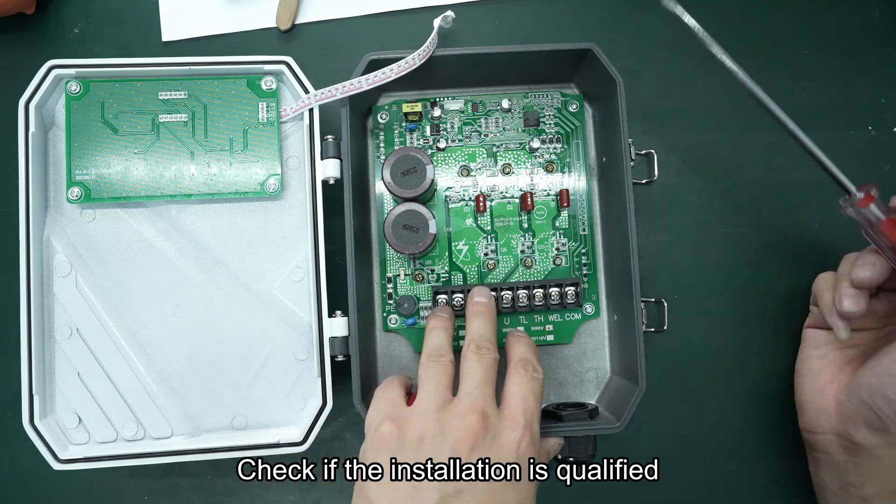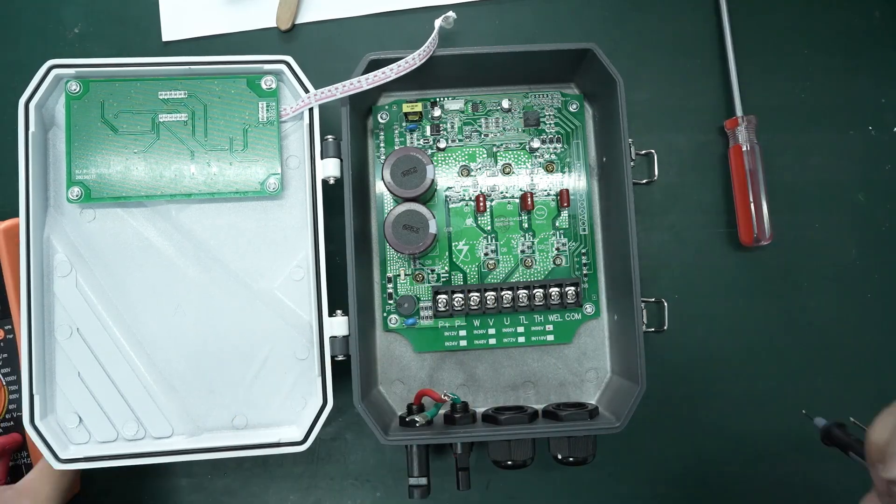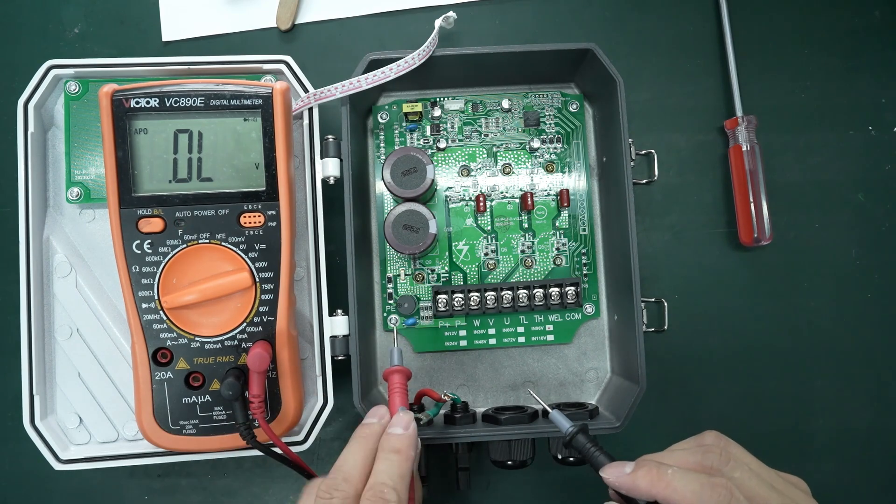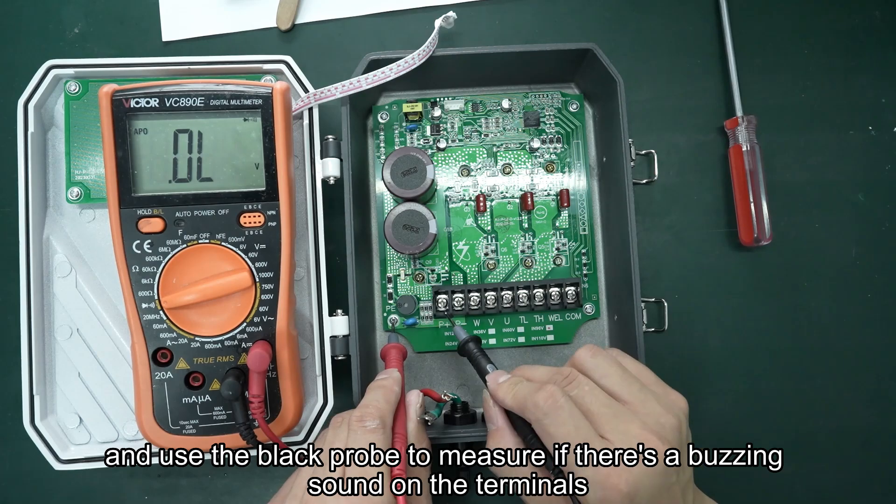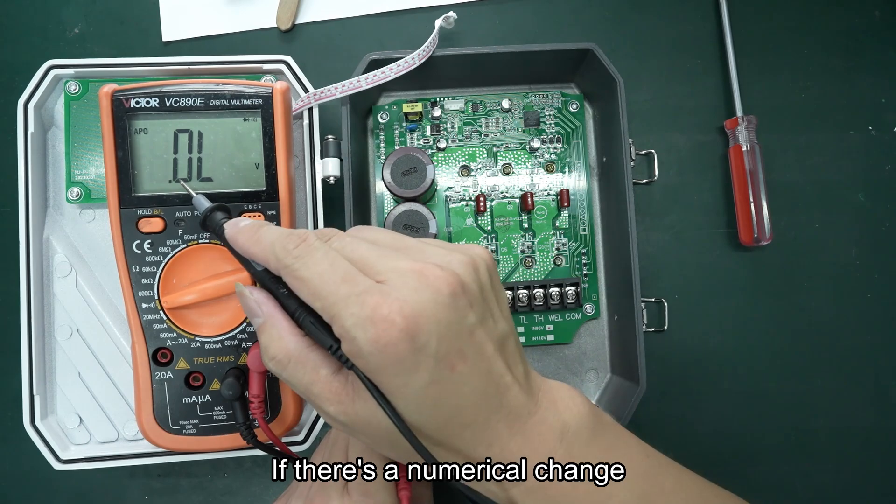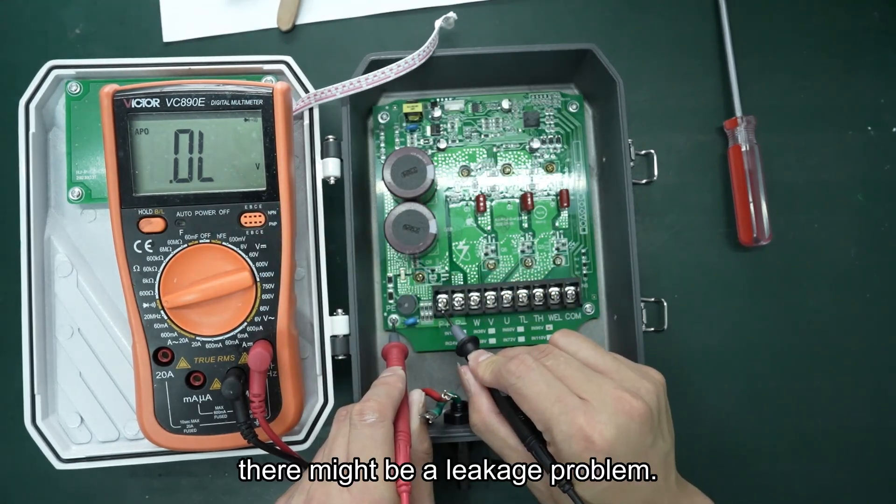Check if the installation is qualified. Use the buzzing mode on the multimeter. Place the red probe on the PE position and use the black probe to measure if there's a buzzing sound on the terminals. If there's a numerical change, there might be a leakage problem.